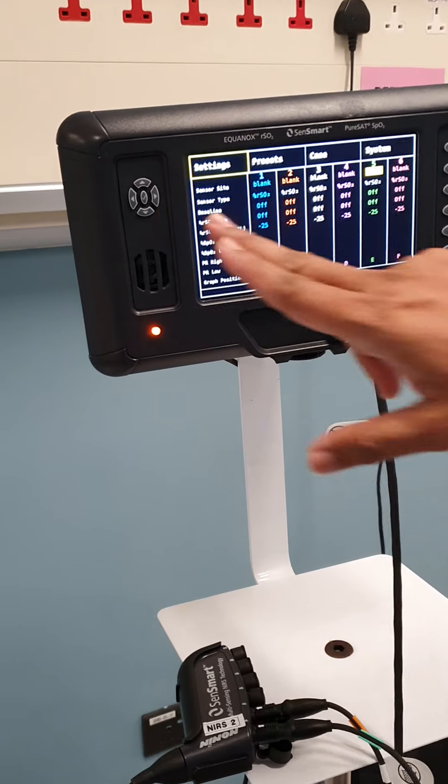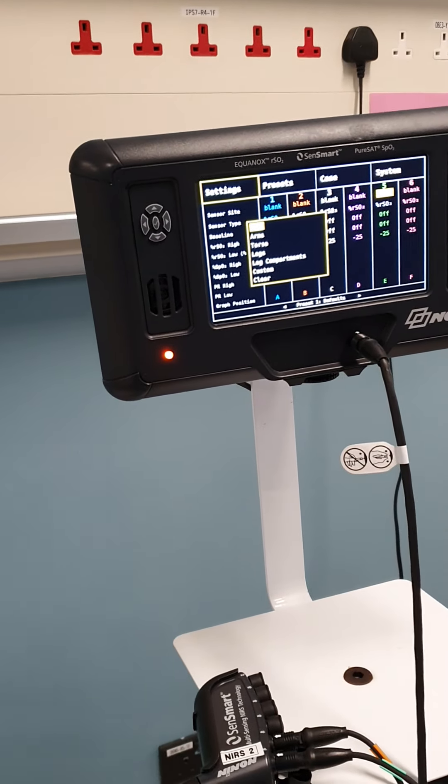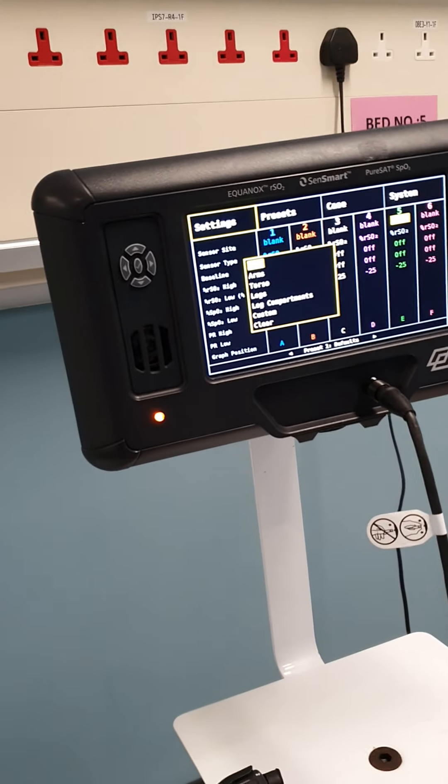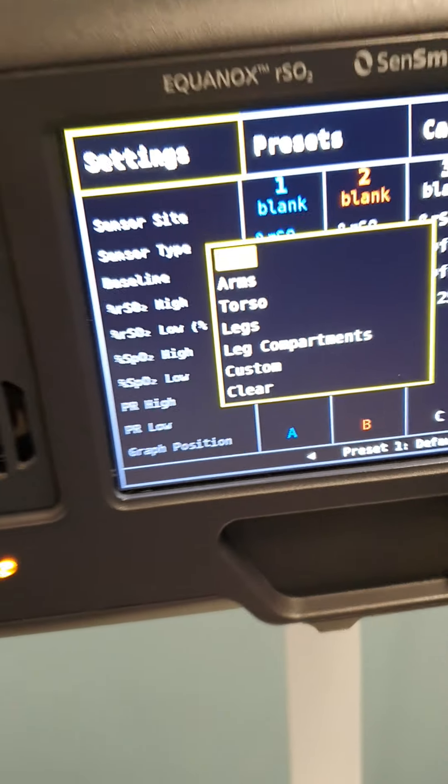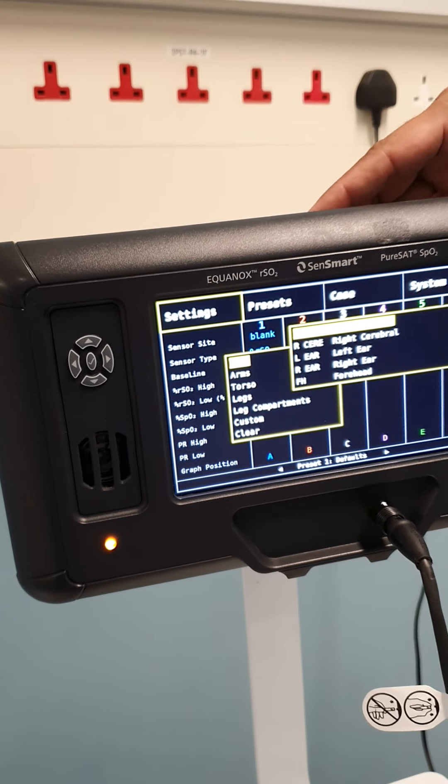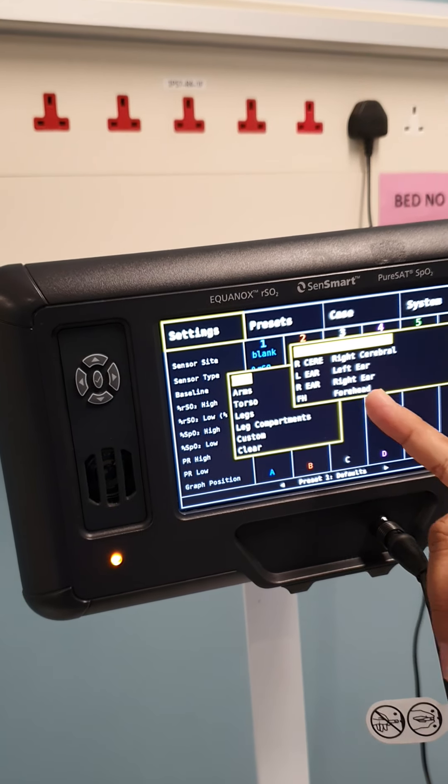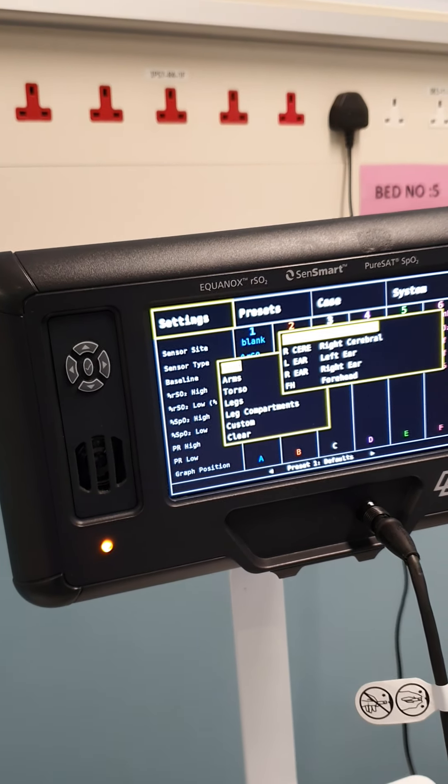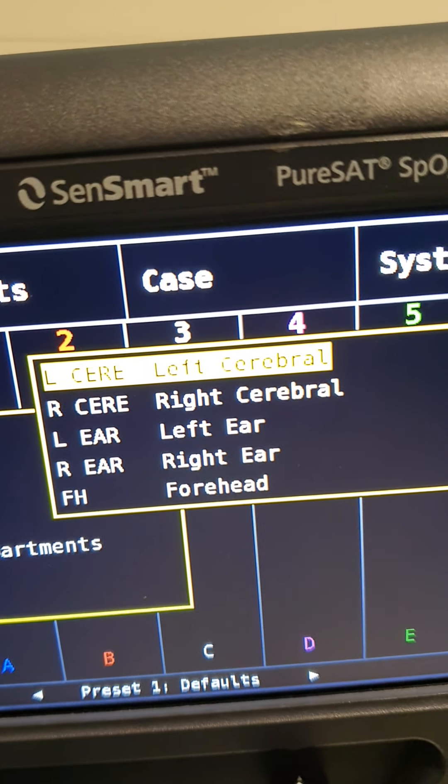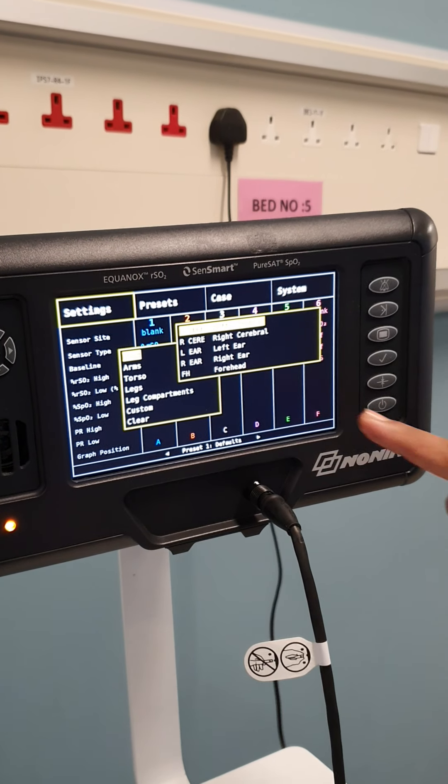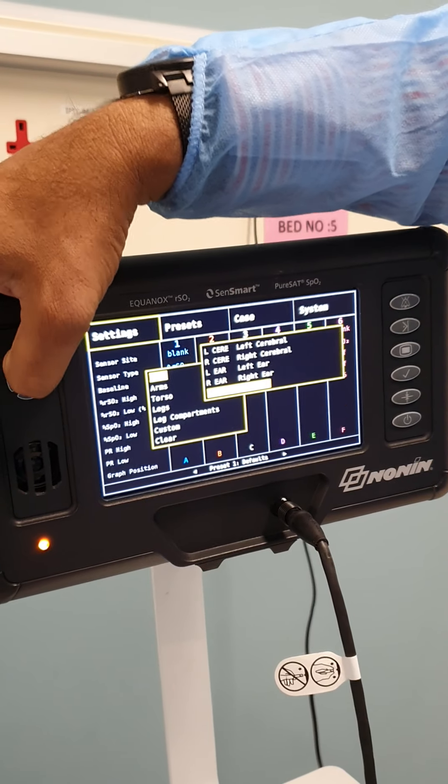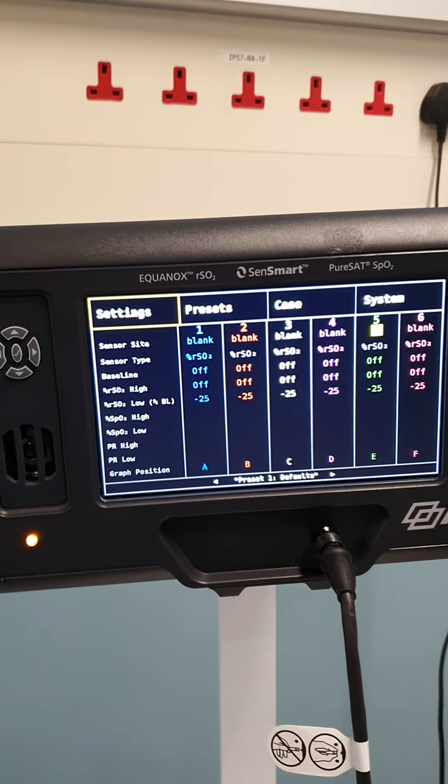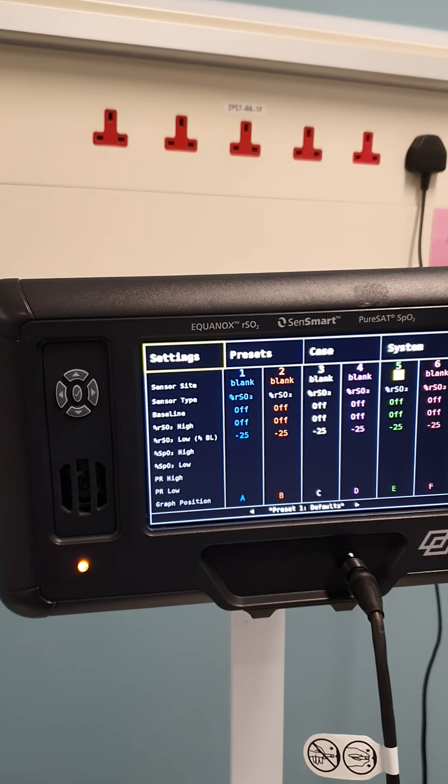Now what we are doing is deciding the sensor type. You can see there are different types we can select: head, arms, torso, legs depending on the patient's condition and the clinical decision by the doctor where he wants to place it. If I put head, you can see we have things like left cerebral, right cerebral, left ear, right ear, and forehead. What we have seen is especially during premature babies with very low weight of 400 grams or less, we may not be able to put two sensors on the cerebral. That's where we prefer to have forehead placement.